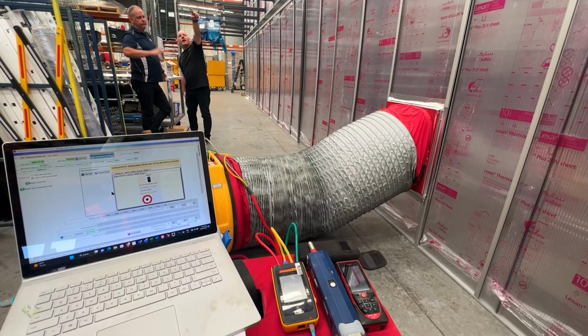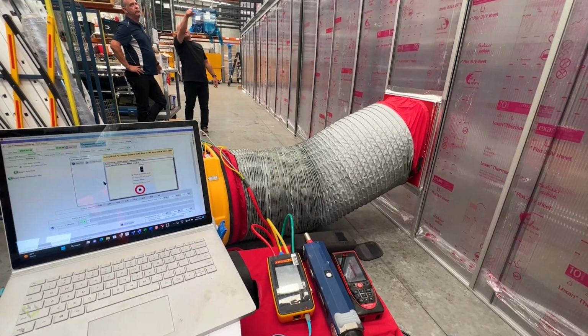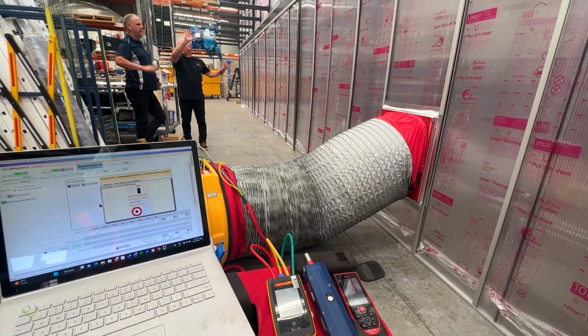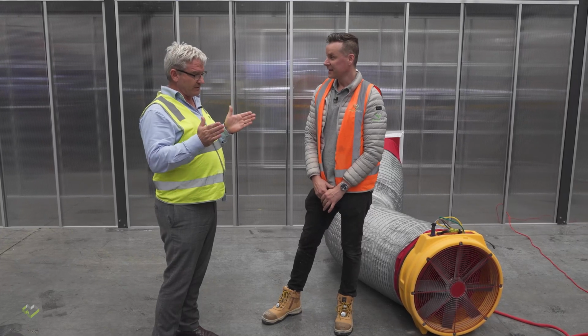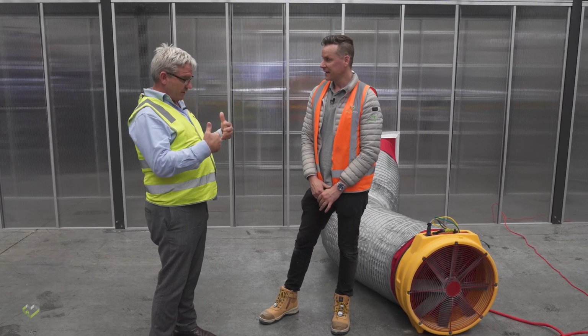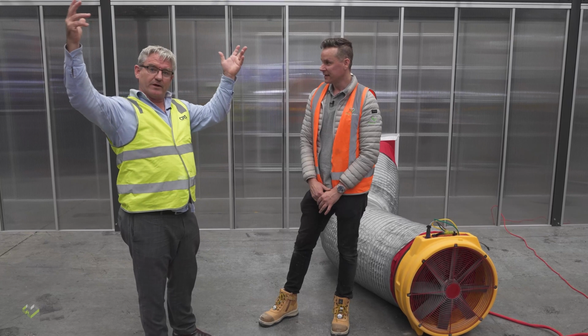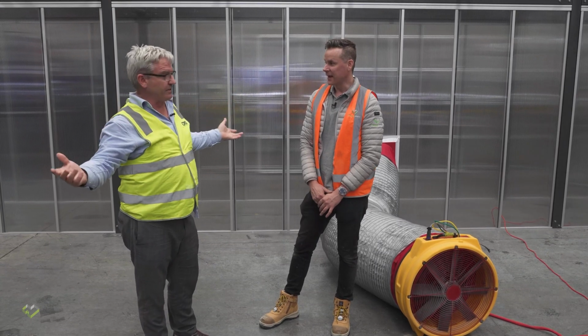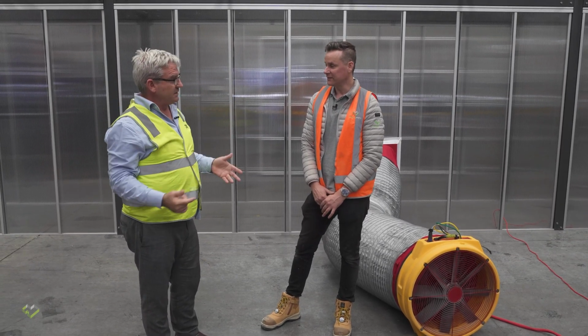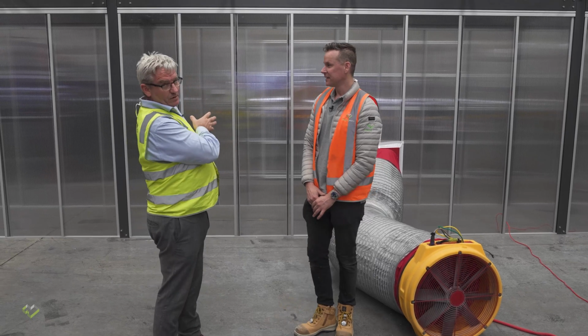Well, obviously with data centers now with PUE, it's very big in the data center environment. Once upon a time you had racks facing racks, so you had a back door blowing onto a front door, very inefficient. Then we turned the racks around, so back door to back door. Then we get the hot air blowing into the one aisle, then we want to remove that hot air so we don't have hot air mixing with the cold air that's coming into the data hall. So to get rid of that hot air, obviously we have hot aisle containment.